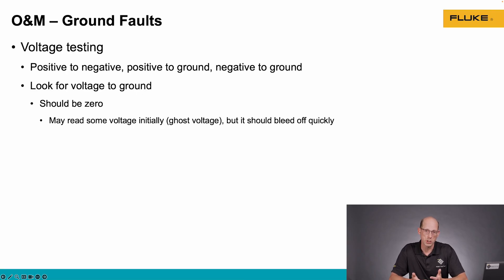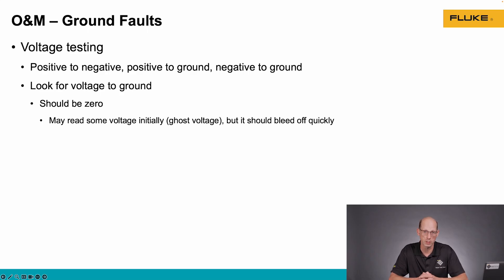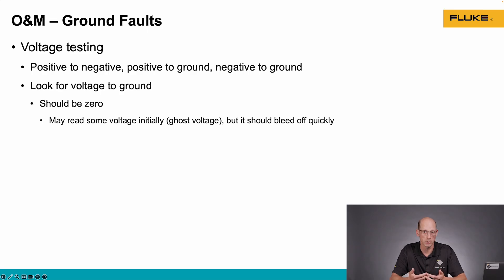We can use voltage testing to identify the location of a ground fault in a string of solar modules. When we test between the positive and the negative of a string of solar modules, we should get the open circuit voltage of the entire string, which is the open circuit voltage of an individual module multiplied by the number of modules in series. In a modern inverter where there's no reference between the positive or negative of the DC array and ground when the inverter is off, if I measure between the positive and ground or the negative to ground when it's operating properly, there should be zero volts to ground. We may see ghost voltage where there's an initial voltage, but that should bleed off pretty quickly.